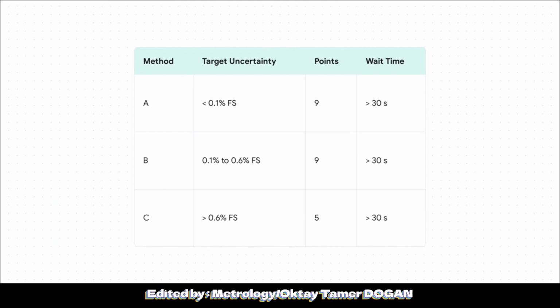Euramet CG17 categorizes calibrations into methods A, B, and C, and this is entirely based on the targeted measurement uncertainty. And you can really see how the strictness scales up. If you want an ultra-precise method A calibration, where you're looking for an uncertainty of less than 0.1%, you have to test 9 different points on the gauge scale, perform 2 full upward and downward cycles, apply 3 preloads just to exercise the gauge, and then wait at least 30 seconds at each point for the pressure to fully stabilize.